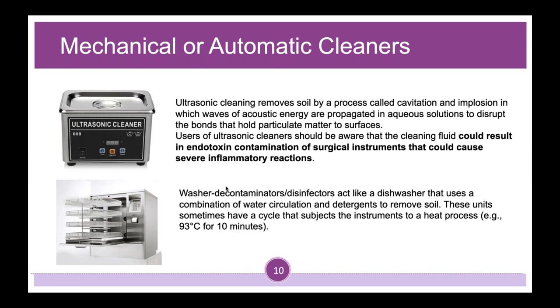Remember that cavitation is associated with your ultrasonic cleaners. It's a process called cavitation and implosion, in which waves of acoustic energy are propagated in aqueous solutions to disrupt the bonds that hold particulate matter to surfaces. Users of ultrasonic cleaners should be aware that the cleaning fluid could result in endotoxic contamination of surgical instruments, which could cause severe inflammatory reactions.